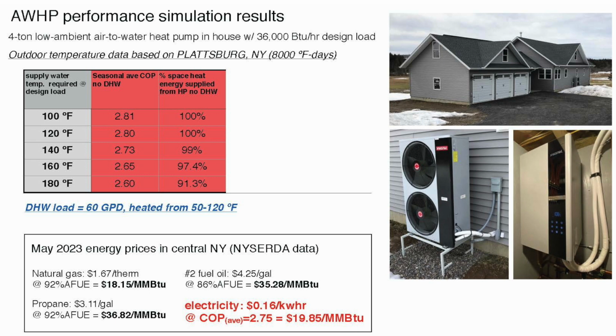And this is basically the supply water temperature required at design load. And I'll cut to the quick. The takeaway is you can use an air-to-water heat pump with a baseboard system. But you need to have supplemental heat in some form. It could be the existing boiler, it could be a new boiler, anything that would provide supplemental heat, and you need to use outdoor reset control.